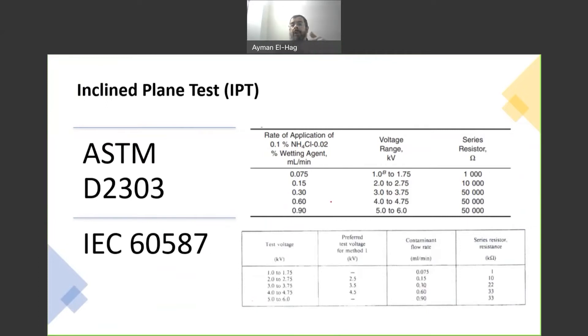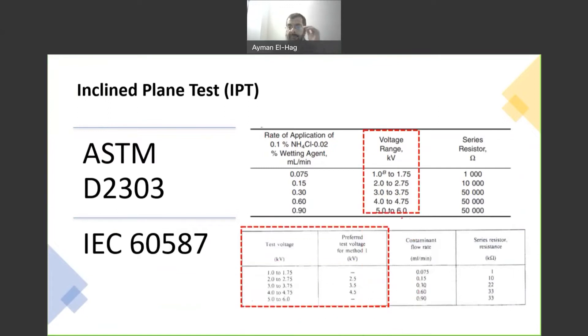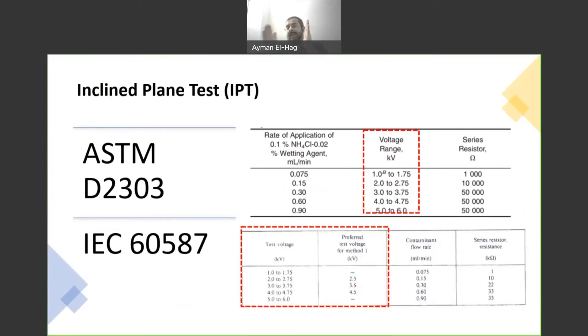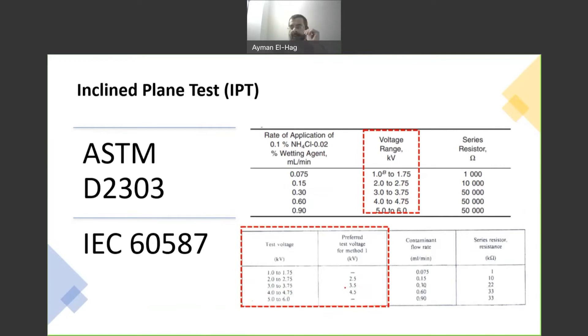In my opinion, these are the two most important tables in each standard — the ASTM and the IEC standard. For the voltage levels, they are almost exactly the same. The IEC standard specifies a preferred voltage closer to the high range; for example, between 3 to 3.75 kV, it suggests using 3.5 kV, and 4 to 4.75 kV, it suggests 4.5 kV. The industry typically uses 4.5 kV as the criterion to test the material.